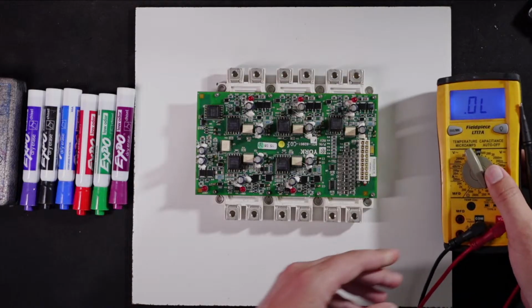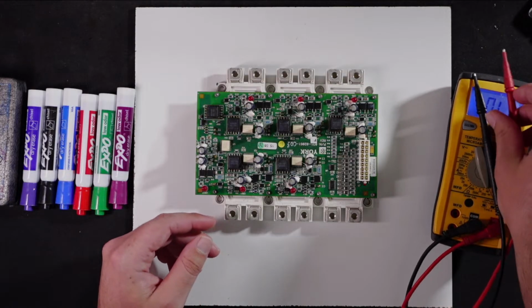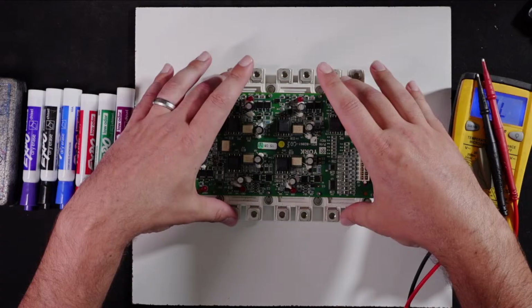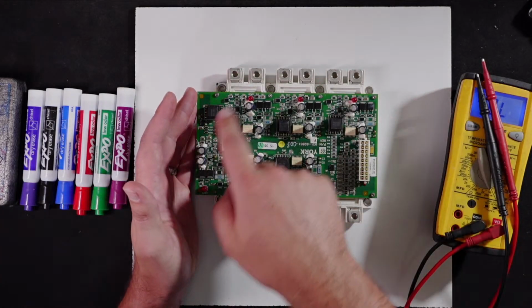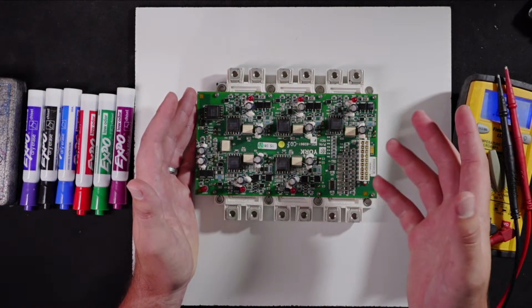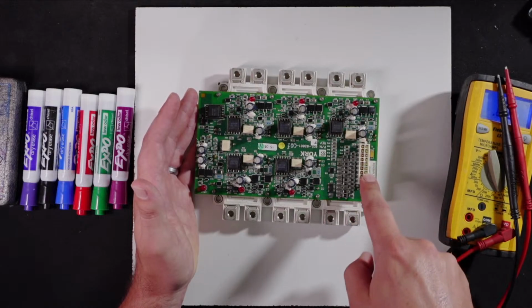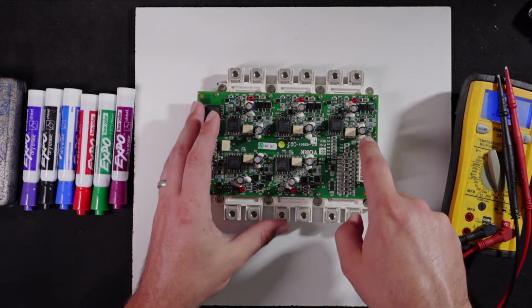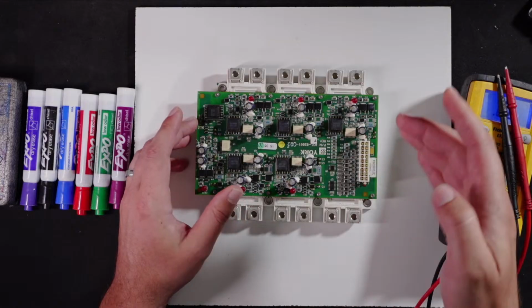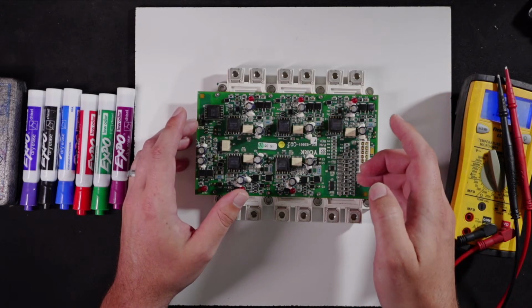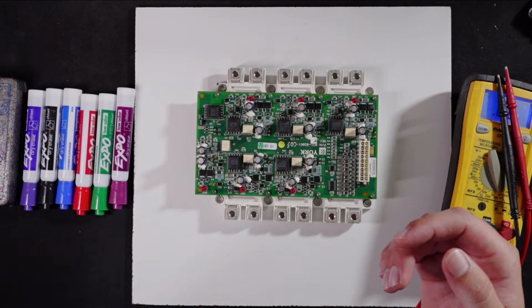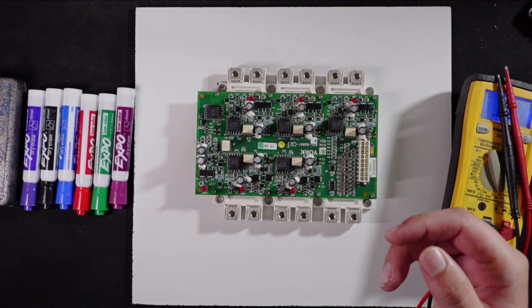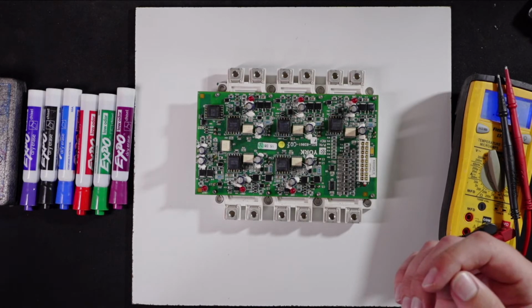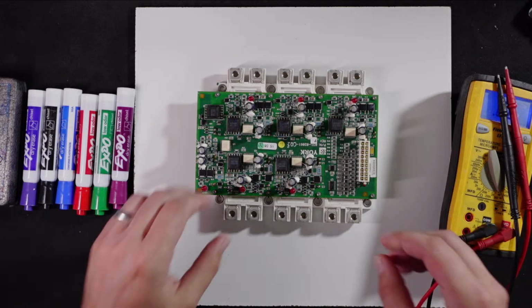And again, the question was, why do they fail? So the heat, the silicon breaks down. You could have any one of these little module components fail. These plugs that go into them are common failure points we struggle with. So you could have a bad plug issue. Taking a little control screwdriver, which I don't have close by, it's in my tool bag out in the shop.